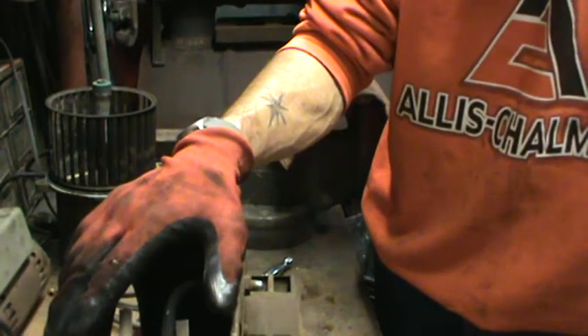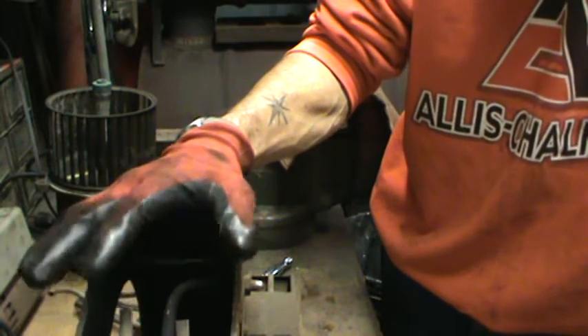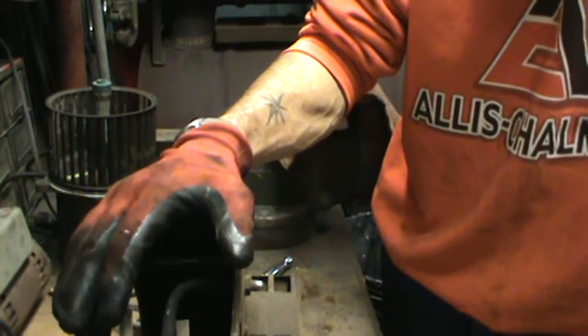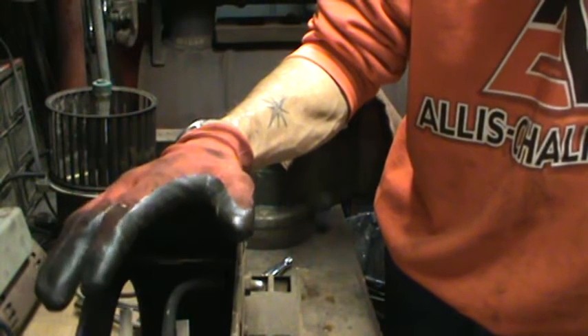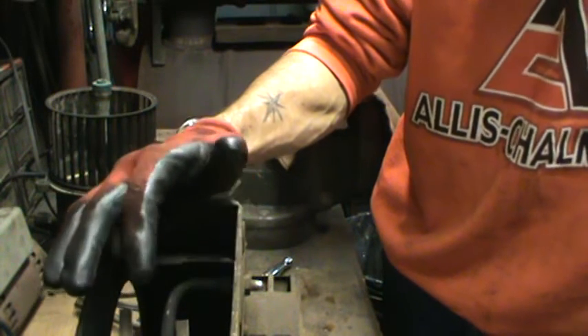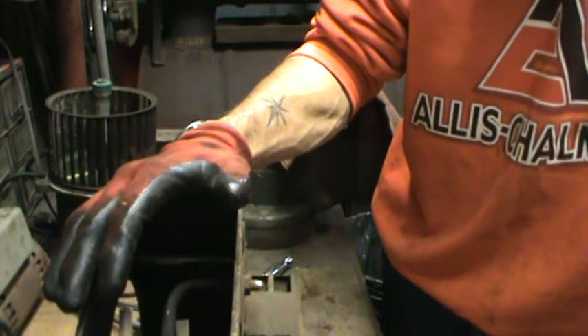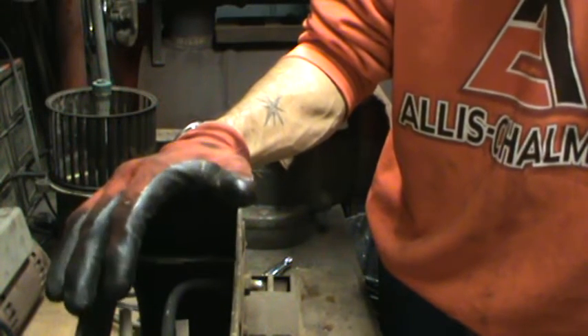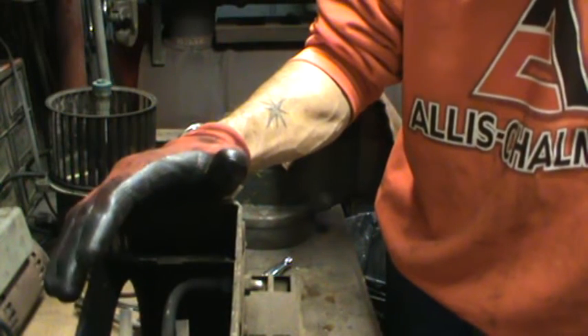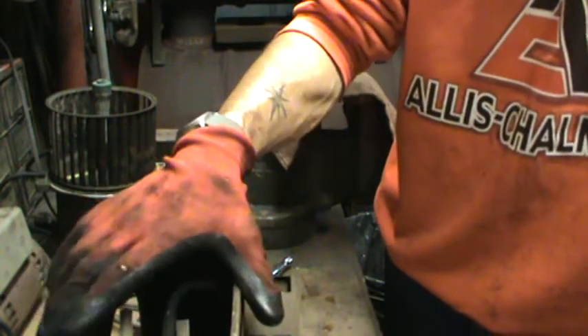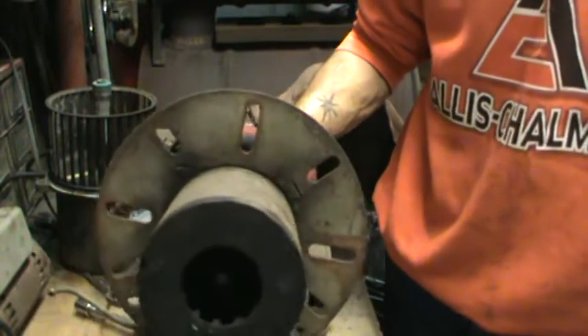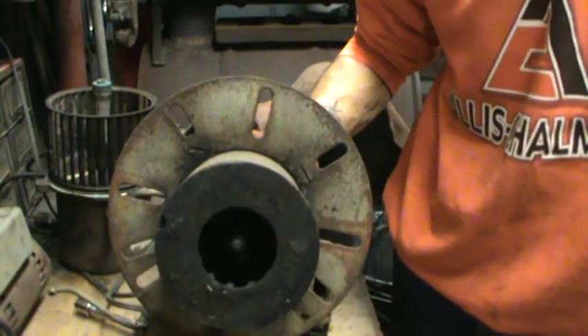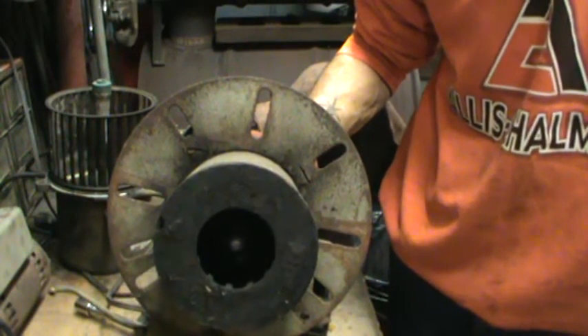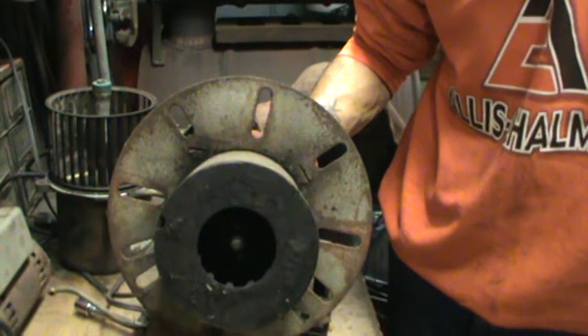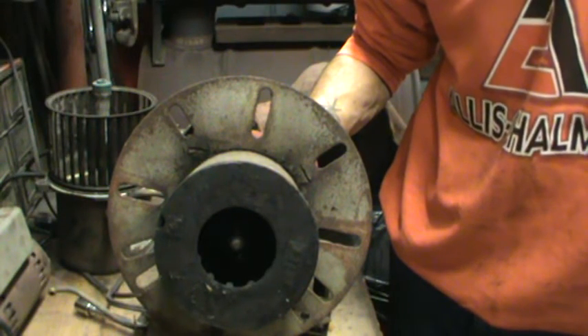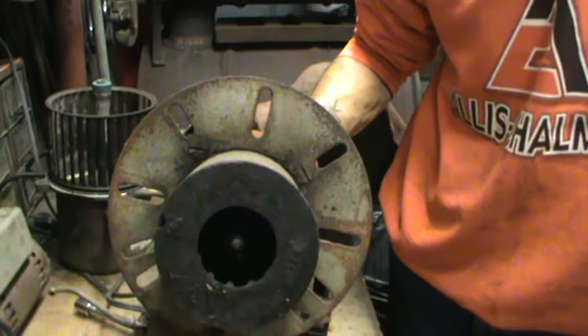But I went through and adjusted the other two heaters to get them to the optimal burn. You don't want any sparks or anything like that thrown out. You don't want too little air where you're suffocating the flame. And there's a sweet balance in a particular color of flame and pattern of flame that you're looking for. And these valves, these nozzles rather, are available in a wide variety of gallons per hour and angle patterns.